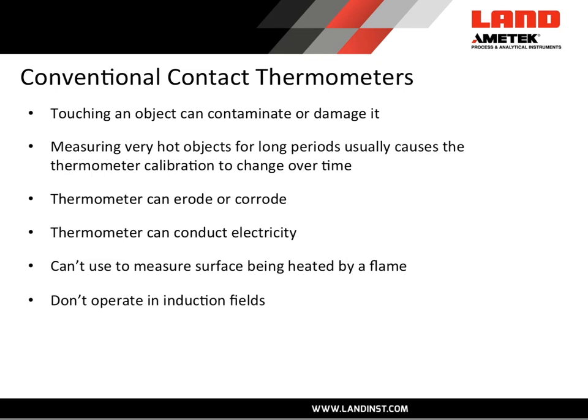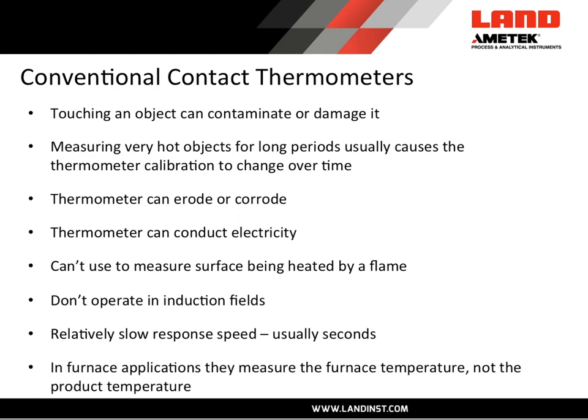A thermocouple or RTD cannot operate in induction fields — those fields would excite the device and give vastly incorrect readings. Thermocouples and RTDs usually have very slow response speeds, even slower if they're in protective sheaths. In furnace applications where you want to measure the temperature of the product, thermocouples are actually measuring the temperature of the furnace and not the product.